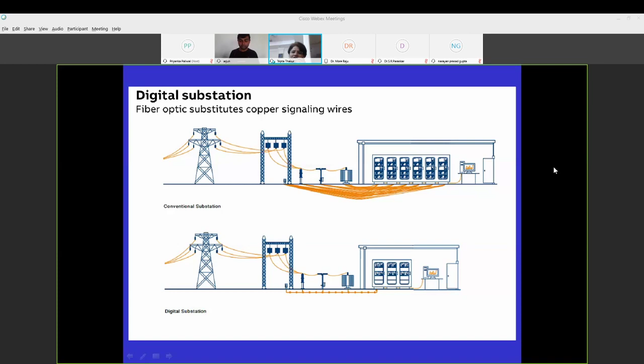So we want to change this station with the help of digitalization into a new digital substation, replacing all the conventional wiring. In the first figure, everything is connected through copper cable in a conventional substation. We are replacing these copper signaling wires with fiber optics. In the second figure, you can see it's very clean because everything is connected through fiber optic substitutes. So the very first step towards the digital substation is to replace all conventional copper signaling wires with fiber optic wires.